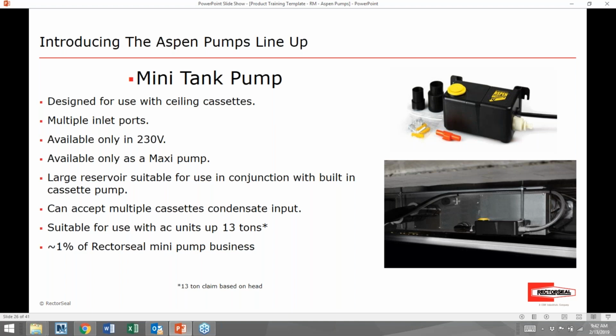It does have a large reservoir, which is suitable to work in conjunction with the built-in cassette pump. So most ceiling cassettes have a small lift pump that's capable of lifting water out about 24 inches. This is really designed just to get the condensate up and over the top of the unit so it can be pumped into a primary drain line of some kind. There's not always a primary drain line available, so the Mini tank pump is a perfect option to have that lift pump right into the tank pump.